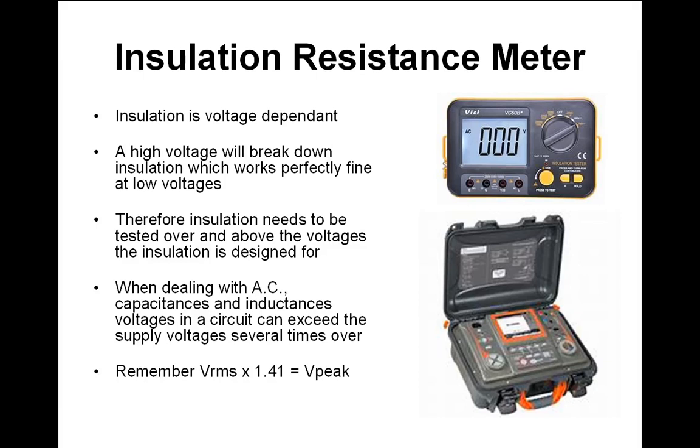Therefore, insulation needs to be tested over the voltage. We did this when dealing with AC capacitance and inductance of voltage. That's another thing as well, just put this in the back of your mind. When we are dealing with circuits that have got inductances and/or capacitances, you can sometimes find voltages well in excess of the operating voltage. And again, a motor is just one big inductor. There are inductances all over the place. Inductance means it's just a coil.